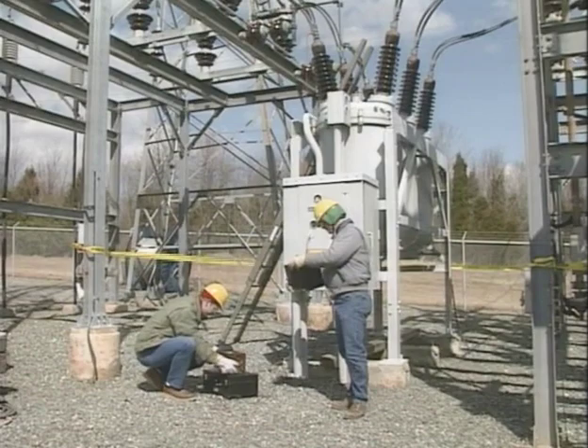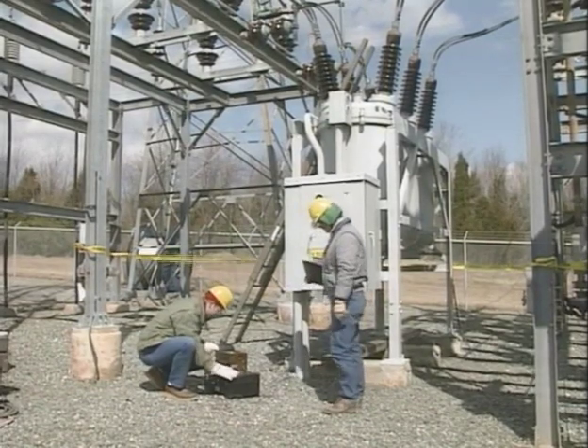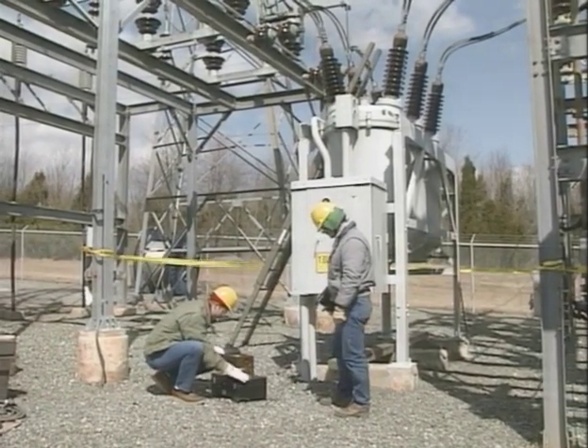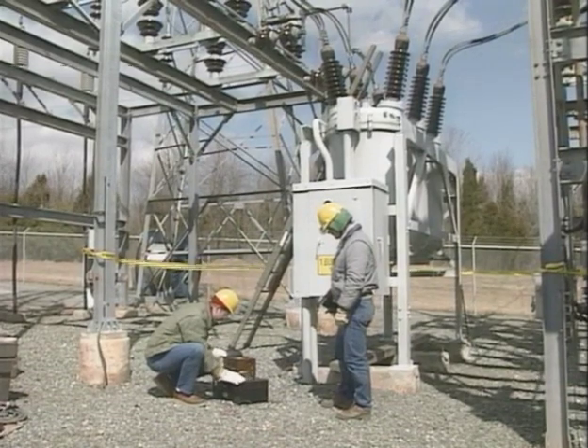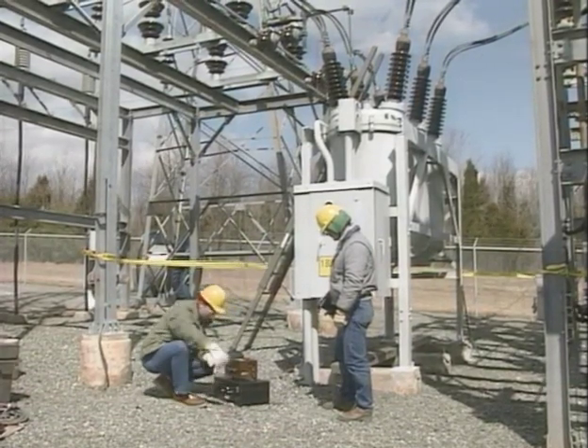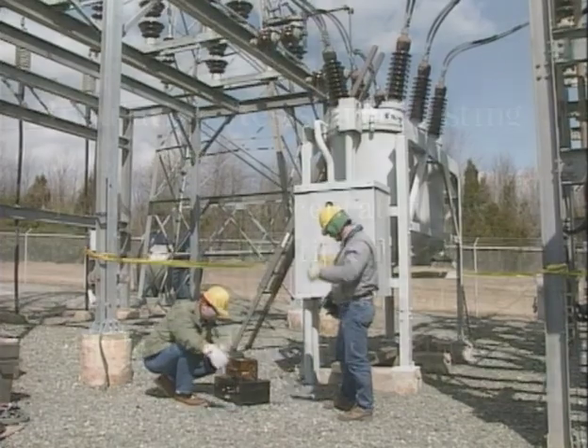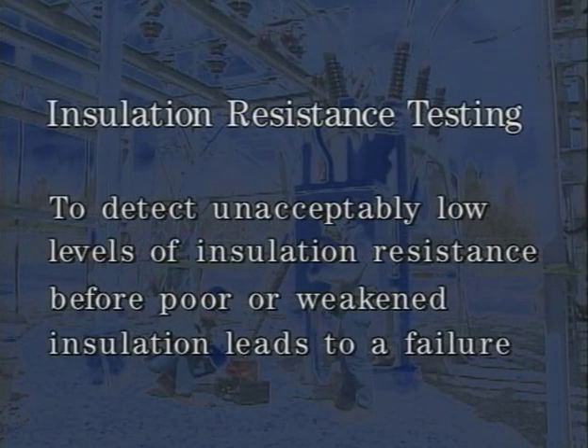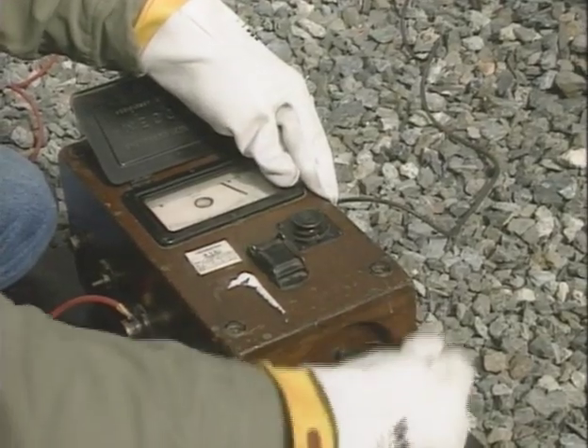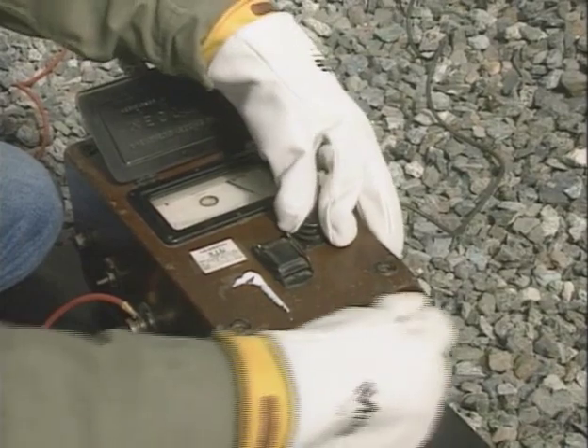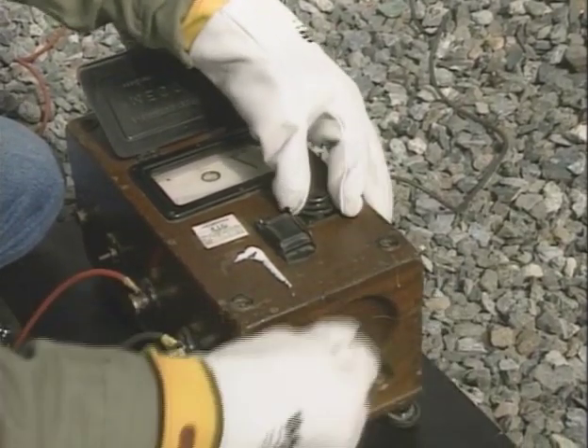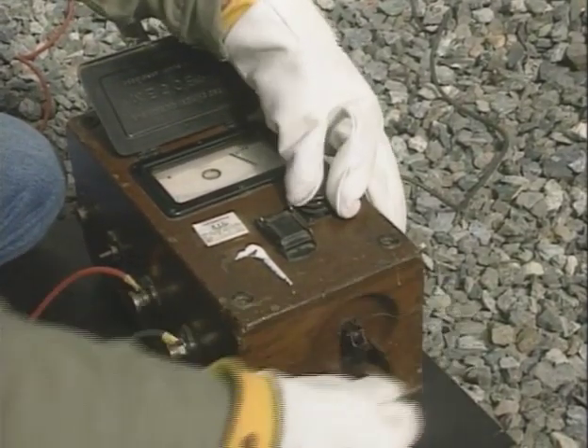A third common proof test is the insulation resistance test. When the circuit breaker contacts are open, the breaker's insulation should provide a high resistance to prevent current from flowing. The purpose of insulation resistance testing is to detect unacceptably low levels of insulation resistance before poor or weakened insulation leads to a failure. In principle, the test is performed by applying a high DC voltage to one of the breaker's bushing terminals with the breaker's contacts open.